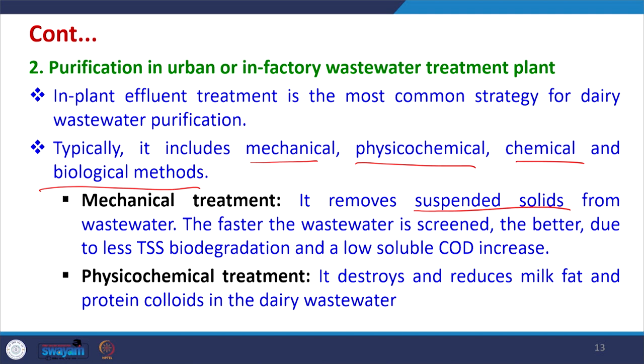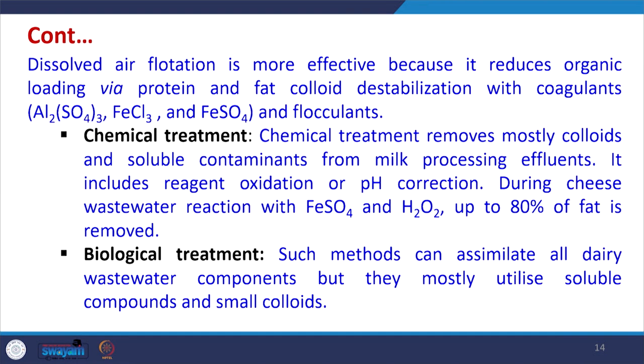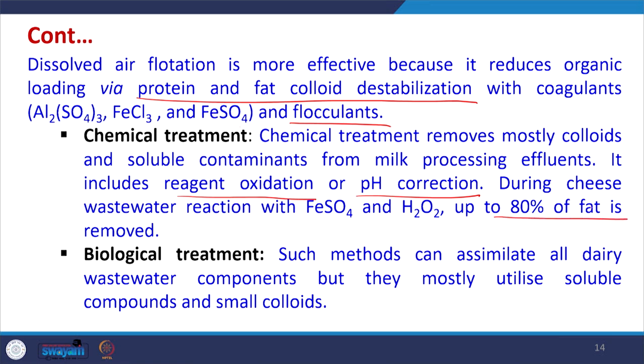Physicochemical treatment destroys and reduces milk fats and protein colloids. Dissolved air flotation is the most effective approach, reducing organic loading via protein and fat colloid destabilization with coagulants such as aluminum sulfate, ferric chloride, ferrous sulfate, and flocculants. Chemical treatment removes mostly colloids and soluble contaminants, including reagent oxidation or pH correction. During cheese wastewater treatment with FeSO4 and H2O2, up to 80 percent of the fat is removed.